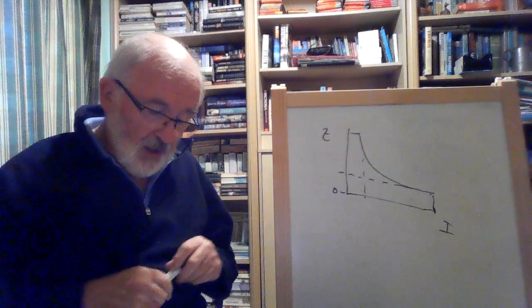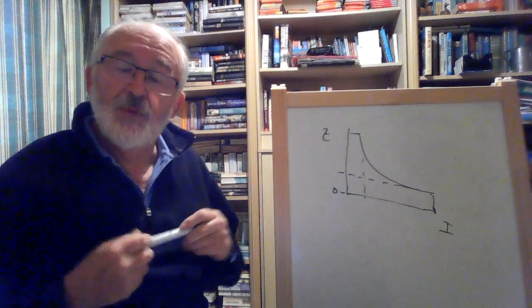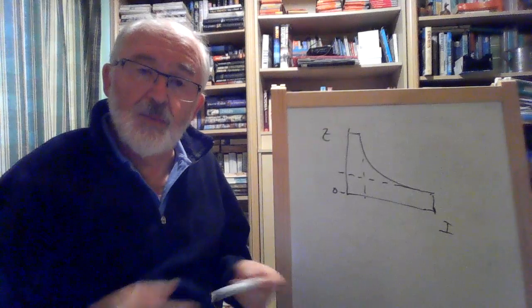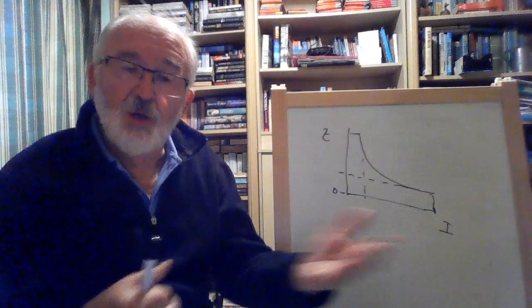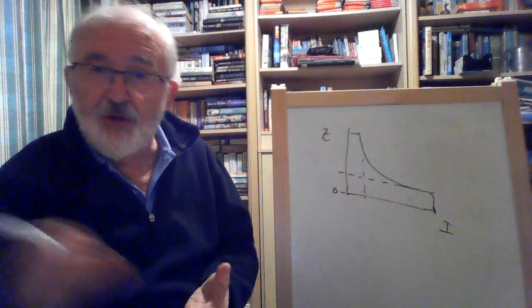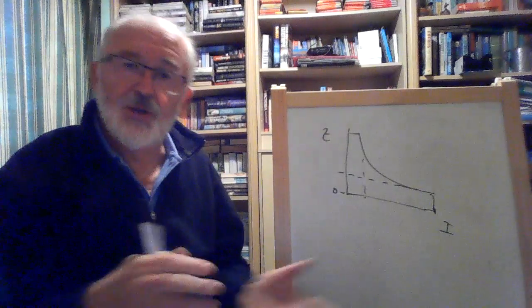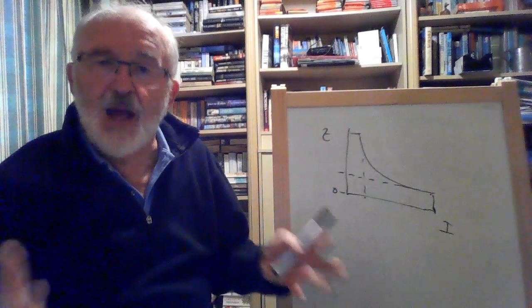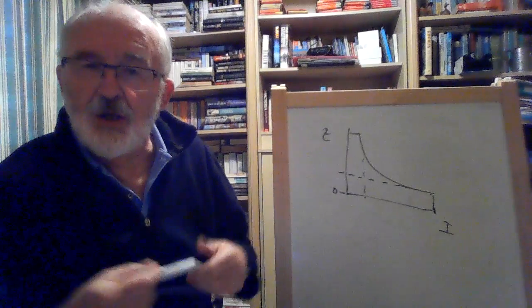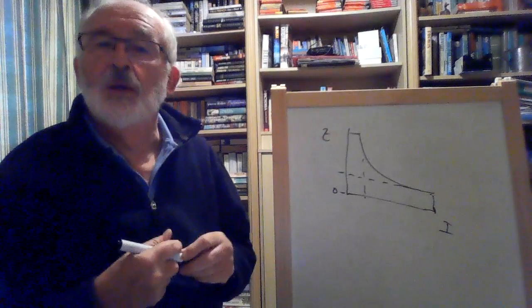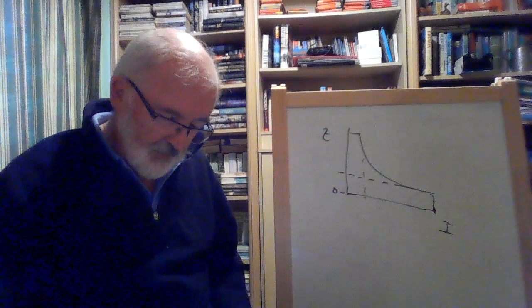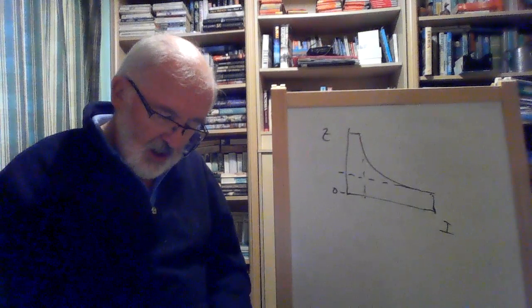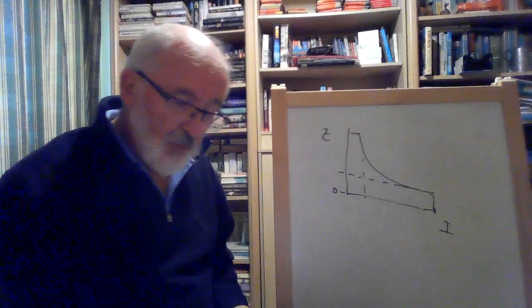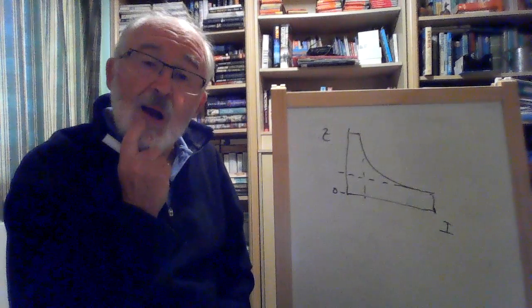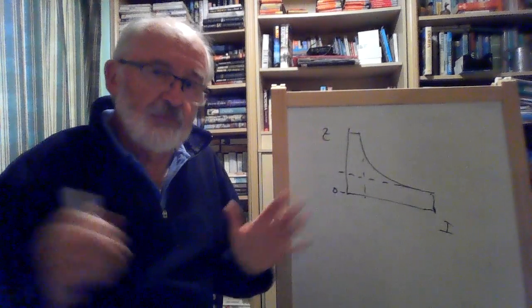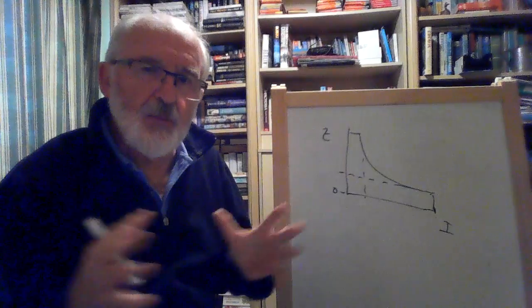If the prime mover fails, then the power from the bus would try to power the generator. So instead of the power coming out of the generator into the bus, power would try and make the generator operate as a motor, which is not desirable. You will black the ship out if that was to happen. So the reverse power trip operates the circuit breaker. So that sums up. There are other protective devices, but they're the main ones that you need to think about.